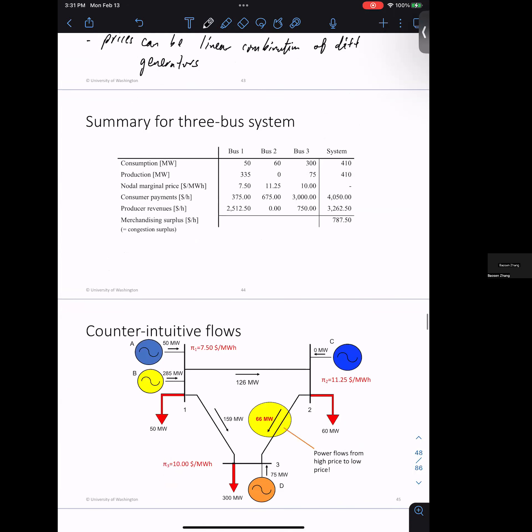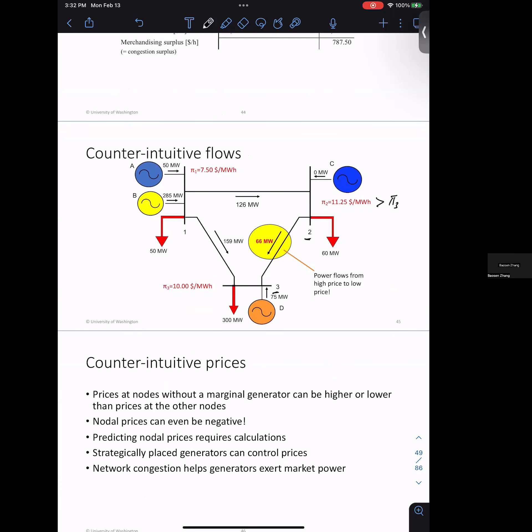You can compute the surplus, consumption, production, and payments across the system. In these kinds of situations, you get very counter-intuitive flows — for example, power flowing from bus two to bus three even though bus two is more expensive than bus three. So power does not always flow from cheaper to more expensive buses. This happens because of Kirchhoff's laws — you cannot route power flow. It is also possible to have negative nodal prices, which is not uncommon.